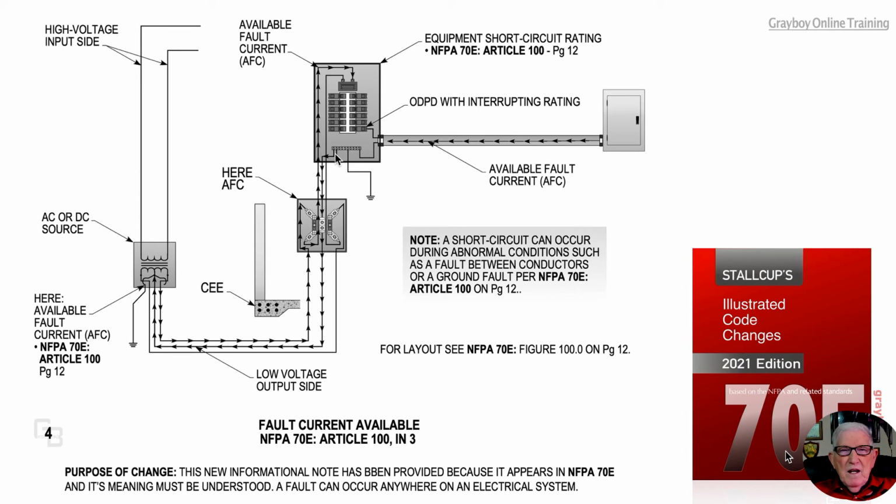Now, NFPA 70B kind of gives a warning to electricians. When you remove the cover here, or just open up the cover, and you review the circuit mapping, if there were more phase-to-phase loads than neutral loads, then this conductor may be just sized from table 250.102, C as in car, 1.